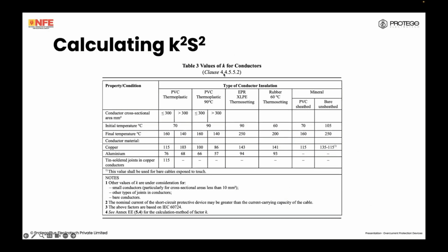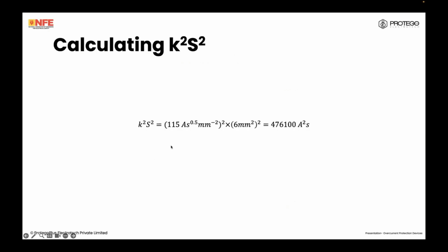If you look at clause 4.4.5.5.2 in the national IS 732, it tells you that for a thermoplastic PVC cable, for a cross-sectional area less than 300 square millimeters, at an initial temperature of 70 and a final temperature of 160, remember, this is our in-load, in-fault, this value for copper is 115. So K squared S squared is going to be 115 squared times 6 squared, which is 476,100 amps squared seconds.